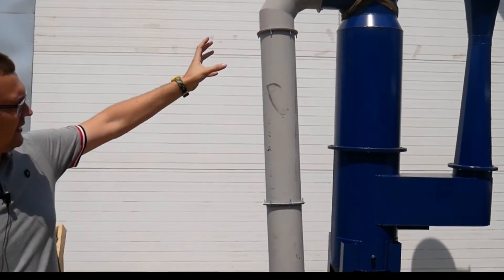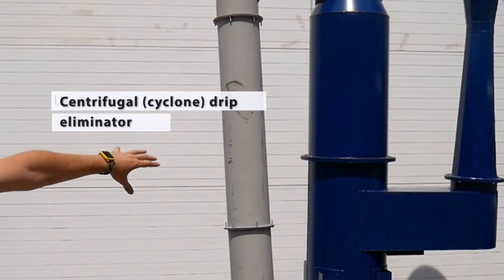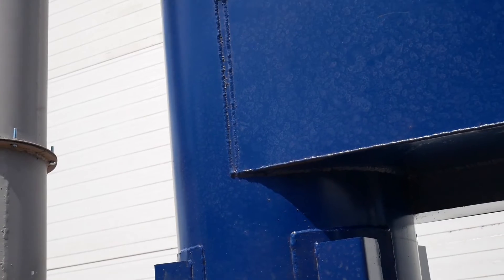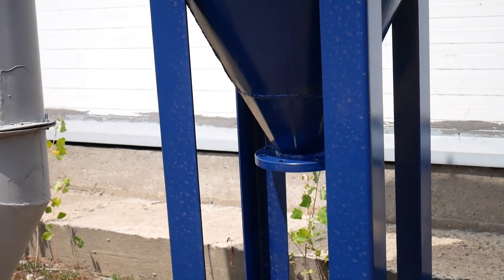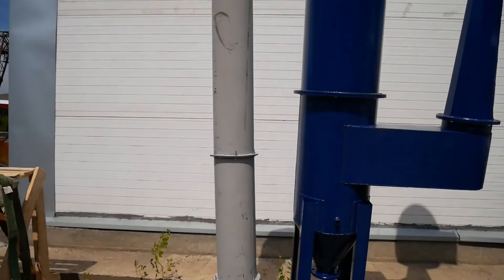Then, water and liquid flow down through the gas duct into a centrifugal drip eliminator. Water with gas flows directly down in the centrifugal drip eliminator because there are heavy particles and they have a certain level of inertia. Meanwhile, the clean air under the draft blower or under the fan goes upwards and passes on ahead.